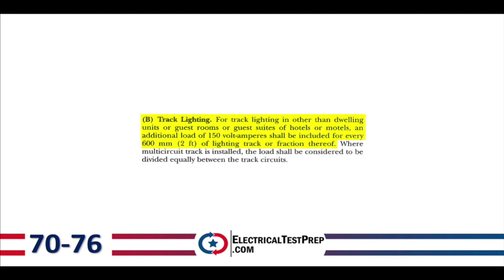Letter B, Track Lighting: for track lighting in other than dwelling units, guest rooms, hotels, or motels, an additional load of 150 volt-amps shall be included for every 2 feet of lighting track or fraction thereof. For a 10-foot track: 150 × 5 = 750 volt-amps.